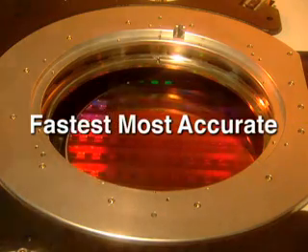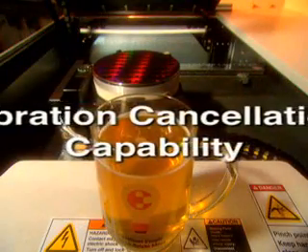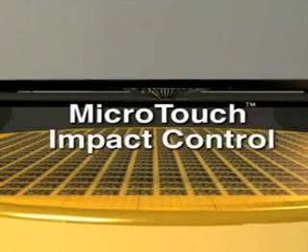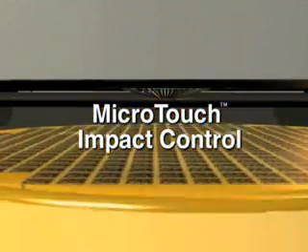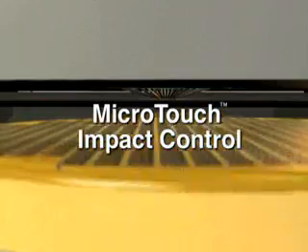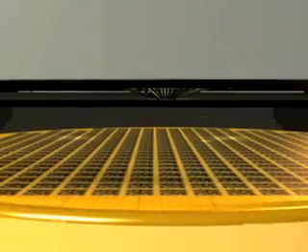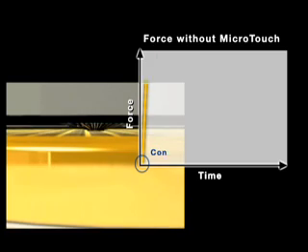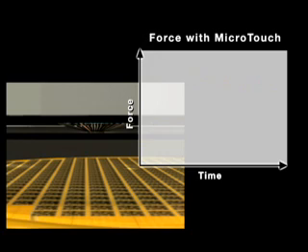Features such as our patent-pending vibration cancellation capability and sophisticated impact control, designed for contacting delicate devices with low-K dielectric or copper technology. Microtouch, for example, is a feature that allows precise control over the contact and impact forces of the probe card needles on the silicon wafer.